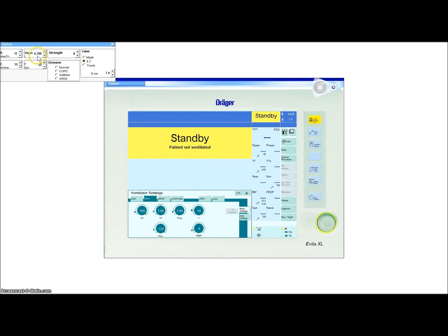Since this is a simulator, I can control the patient's lung dynamics. The patient is breathing at a rate of 25, yet I have the sensitivity, the strength, set to 0. Therefore, he is actually not breathing. His lung compliance is 30. His resistance is 11. His tidal volume is 700, but since he's not breathing, he's not going to create that tidal volume. And notice he has an endotracheal tube, a 7.5 ET tube. Excuse me, 7.0. I'm going to change that to 7.5 because I have automatic tube compensation, and that's what it's set to.